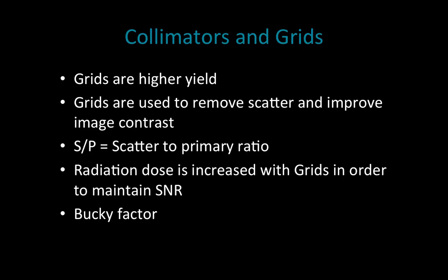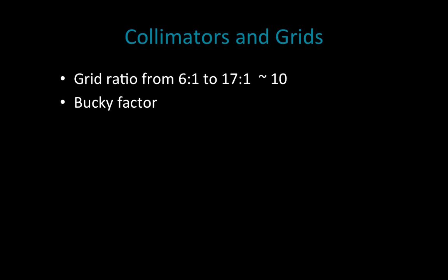Sometimes you can have up to five times more radiation with a large bucky factor. The grid ratio is correlated with the lead strips in your grid — you measure the height over the width of those strips. The smaller the width between strips, the higher the ratio. A very high grid ratio means you're placing many strips in a small area, creating a higher grid factor and tending to create a higher bucky factor.